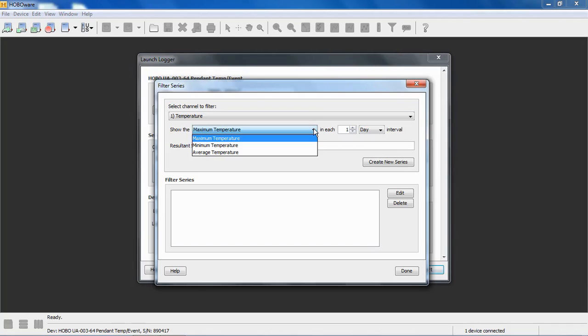In this case, you can select for the temperature channel, you can select maximum, minimum, or average over a range of measured or logged data points. For example, if you were logging temperature every five minutes and you select maximum temperature in a day, HoboWare, when you read out the data, will look at each day's worth of five-minute intervals of data and determine the maximum temperature and record that. So you will have one data point for each day that represents the maximum temperature that it saw at those five-minute intervals.